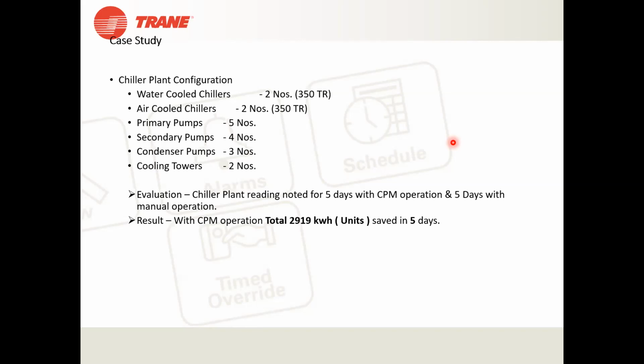What is the difference between air cooled and water cooled chillers? In air cooled, the refrigerant runs through a series of condenser coil banks with vertical exhaust fans, and the fans draw air through the coil, transferring heat from the refrigerant to the atmosphere. In simple language, you are using air to cool down your refrigerant. In water cooled, you are using condenser water to cool down your refrigerant temperature. That is the basic difference.